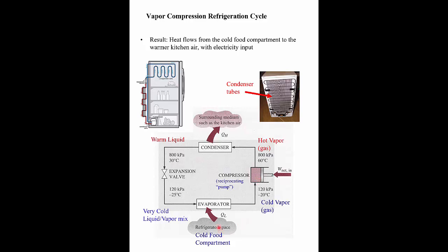The net result is you've picked up heat from the food — Q low — and you've dumped heat to the kitchen through the condenser. That's the basic function of a vapor compression refrigeration cycle. Here's a picture of an actual refrigerator: this is the compressor, the hot gases come out and go into the condenser on the back of the fridge, there's the expansion valve that cools the gas down to very cold temperatures, and it goes inside the refrigerator where it picks up heat from the food, then goes back to the compressor.